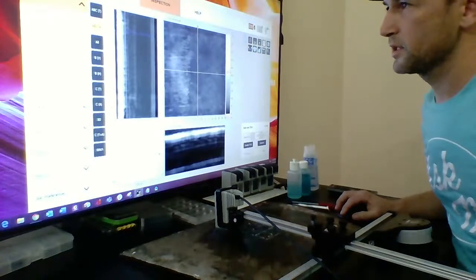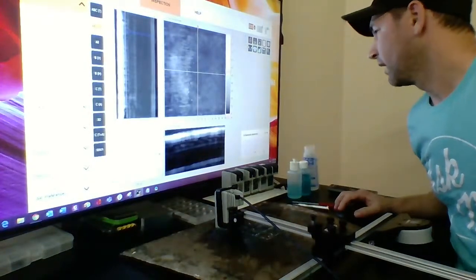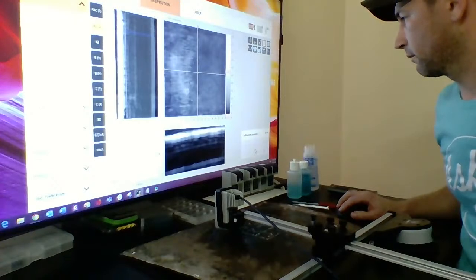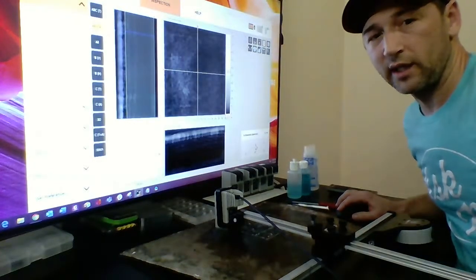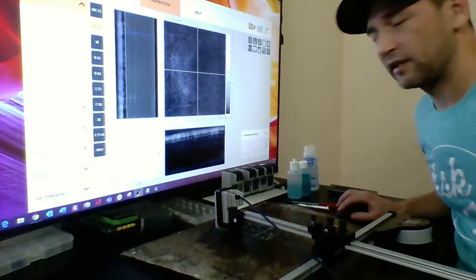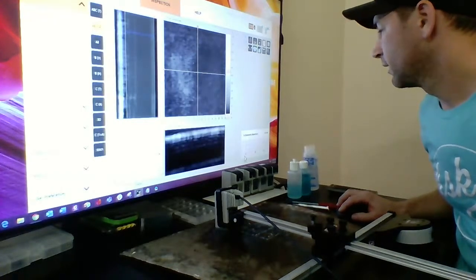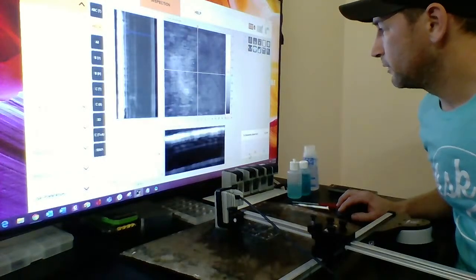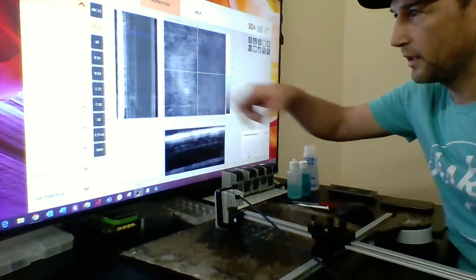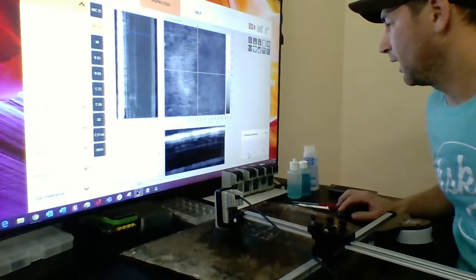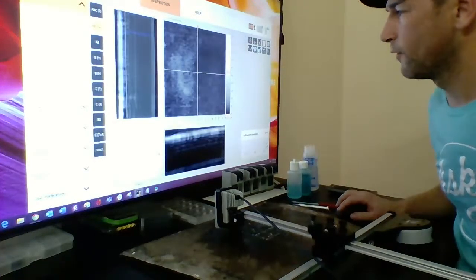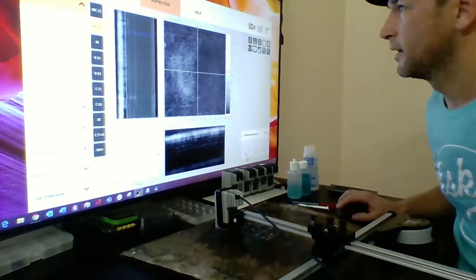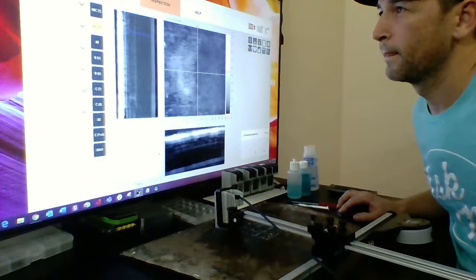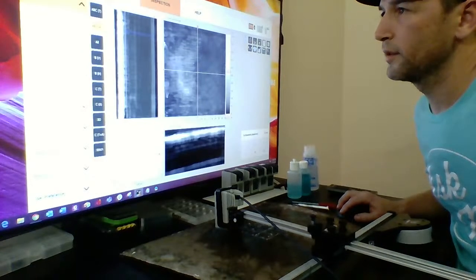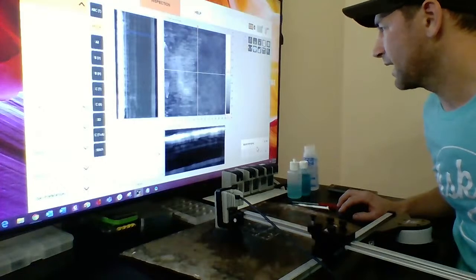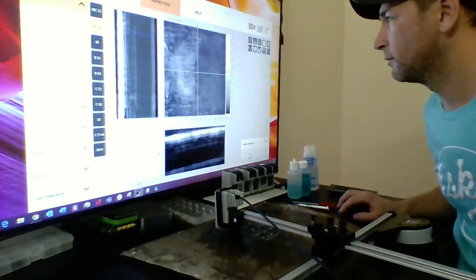which we've already adjusted. And then we have our transmitting elements. We can adjust the amount of energy going into the part to give us better detectability and resolution. As you can see, you start intensifying the signal here by increasing the number of transmitting elements. Let's try 4. I like 8 better, so we're going to adjust it to 8. Then we have signal averaging. I have it set to 4. It's a good in-between.